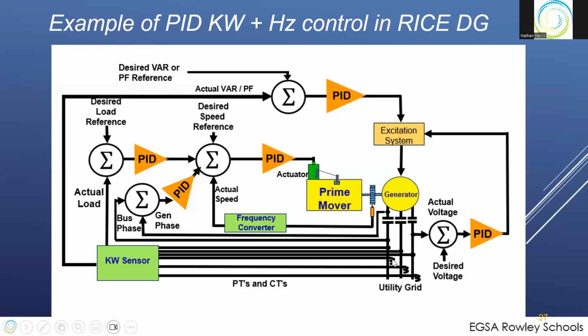And so now you have watt feedback with your KW sensor looking at your voltages and your currents, producing a KW signal and a kVAR signal. The KW signal goes into your load reference. So now your load regulator, that is your KW regulator, the PID for the KW regulator, provides a speed trim signal into this regulator. Because we have multiple regulators running, the time constants have to be set so they don't interact with each other. Typically, you'll set the inner loop faster than the outer loop so that you don't have this oscillatory effect. That figure is normally a 3-to-1 response separation if you're measuring response in radians.